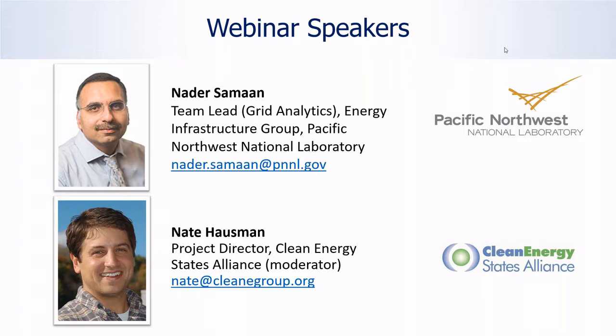Ideally, you would like to do that in real time, but currently Duke Energy's DMS, the distribution management system, doesn't have communication with the utility scale solar connected to their system. But we are doing that through the OPAL-RT simulations and exploring several modes of operation and different communication protocols. So there is no one certain protocol that we are recommending at this point, saying this one is better than that one. We are still investigating that further.